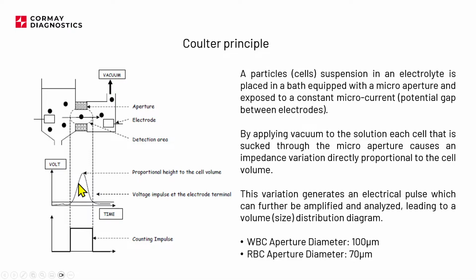So keep in mind, two pieces of information are recorded when the cell is passing through the aperture. We are recording the size or volume of the cell, right? So we can differentiate if this is lymphocytes, mid-sized cells, or granulocytes. Or in the PLT RBC channel, we can differentiate between platelets and red blood cells. We can even say how big those platelets and RBCs are, because later the device is building the histograms. And the counting impulse.